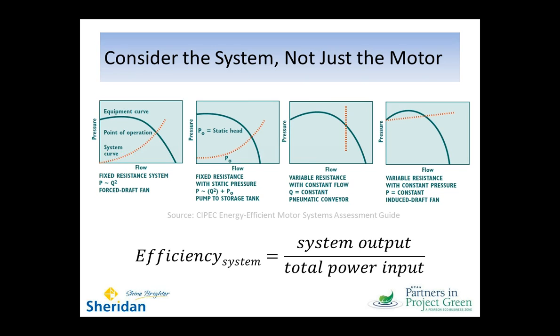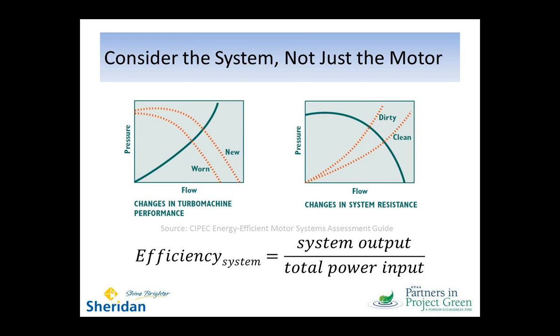Not all of our controls are created equal. To make things worse, as our system ages, the system characteristics change. First, what we might find is that our turbo machinery, our pumps and fans, as they wear, are no longer providing the same amounts of flow at the different pressure regimes. So we've moved off that optimal curve. The second thing is that our system may move from a flow versus pressure regime to a steeper one, where, as I've got clogged filters and dusty components, I'm essentially building more pressure, or more resistance to my flow, as that system gets dirty. So maintenance is obviously a key factor in here.